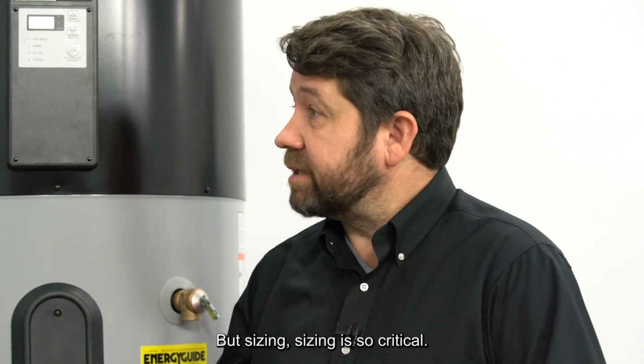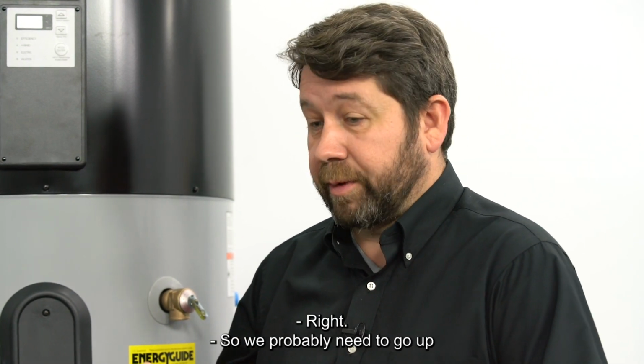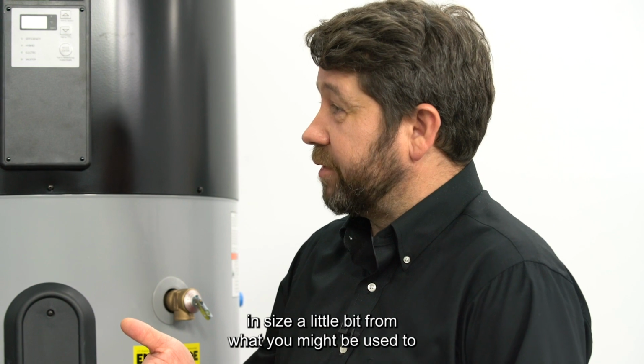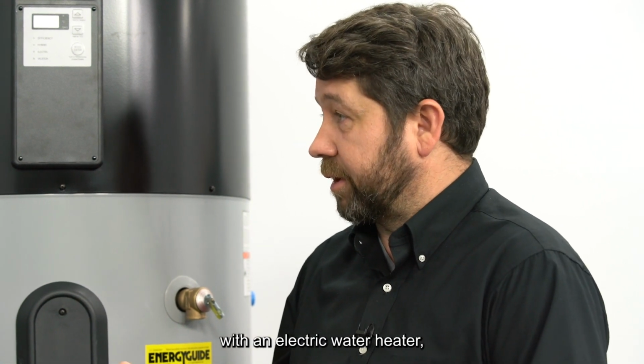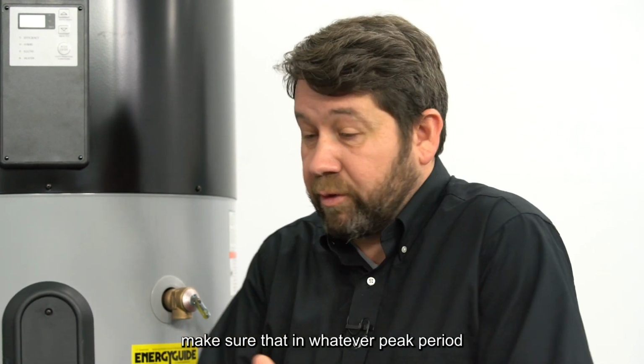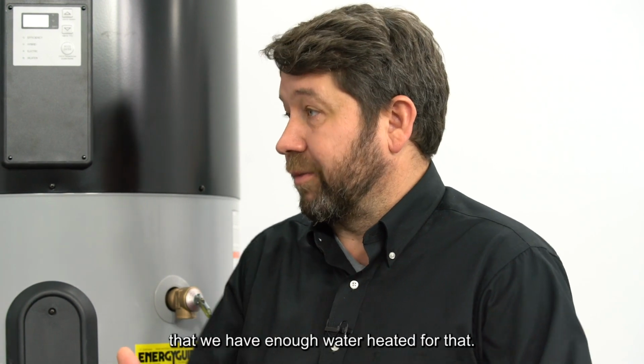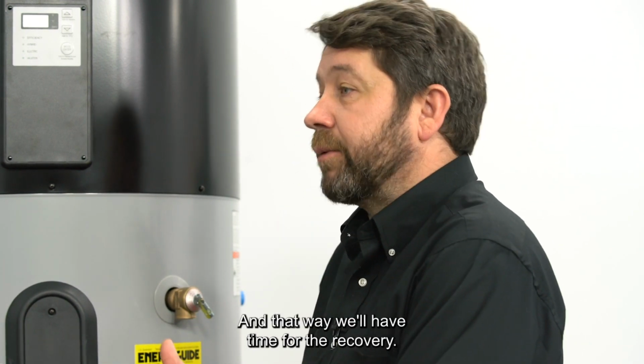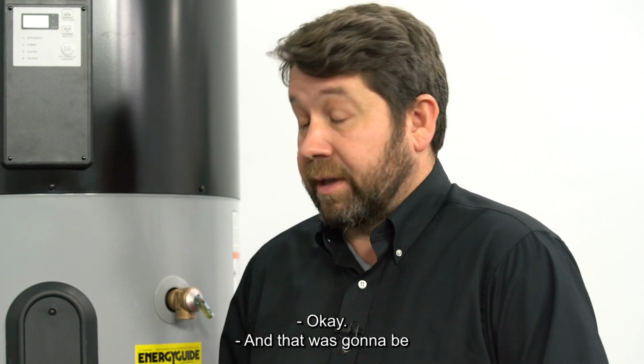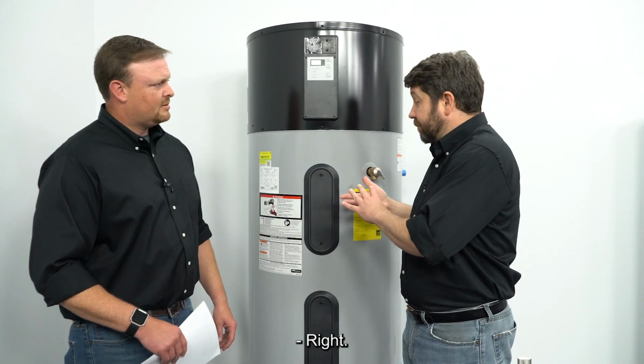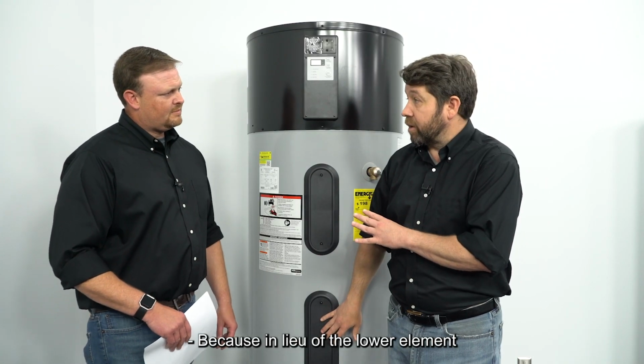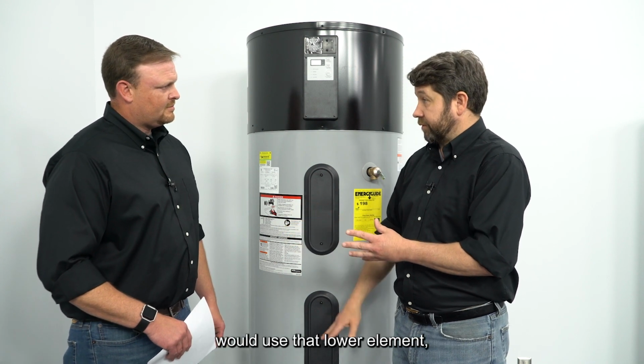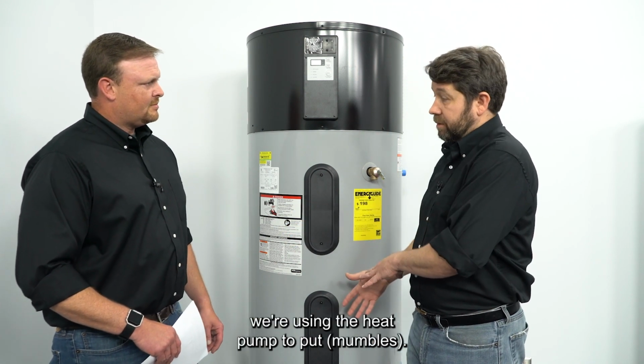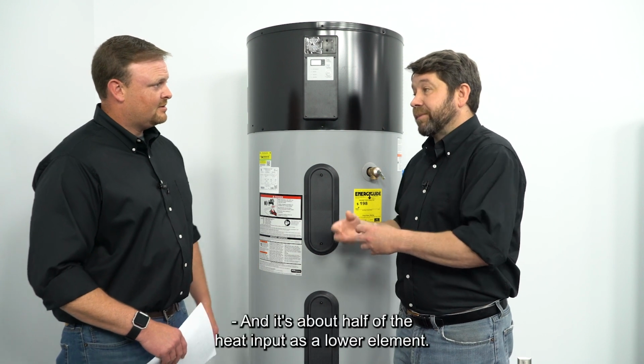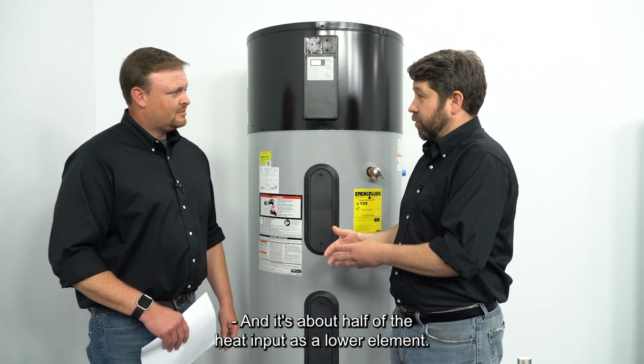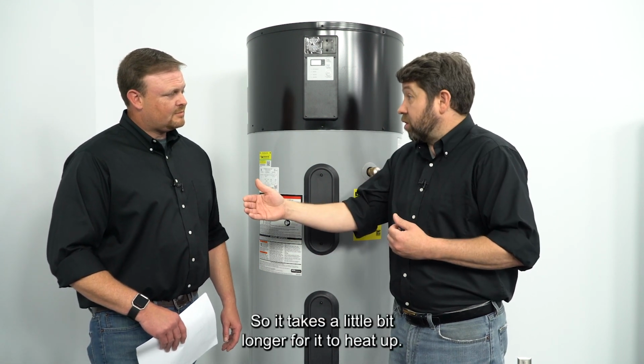But sizing is so critical. So we probably need to go up in size a little bit from what you might be used to with an electric water heater. Make sure that in whatever peak period we're going to use hot water, we have enough water heated for that, and that way we'll have time for the recovery. That's going to be the other side of this. Because in lieu of the lower element, where a traditional electric water heater would use that lower element, we're using the heat pump, and it's about half of the heat input of a lower element. So it takes a little bit longer for it to heat up.